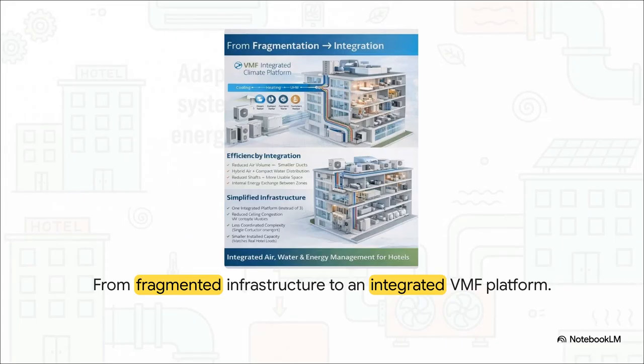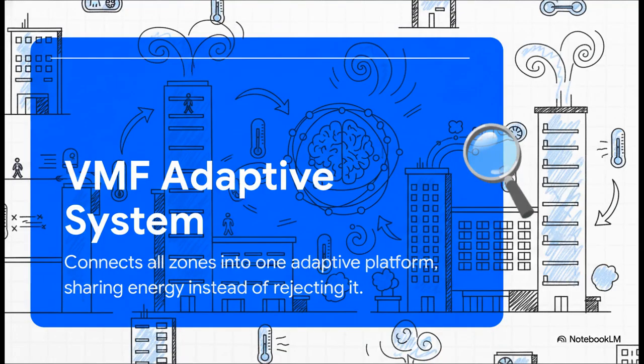Which brings us to section two, VMF, the integrated solution. Notice the stark visual contrast here. We're moving away from those separate, totally disconnected systems that just crowd up your ceilings, over to one unified, simplified VMF platform. Up top, you've got the old, fragmented infrastructure, separate VRF units, air handlers, and boilers that completely ignore each other. They don't communicate, and they certainly don't share energy. But below that, that's the beauty of integration: you get reduced air volume, which means smaller ducts, fewer vertical shafts eating up your valuable real estate, and a drastically cleaner ceiling layout.